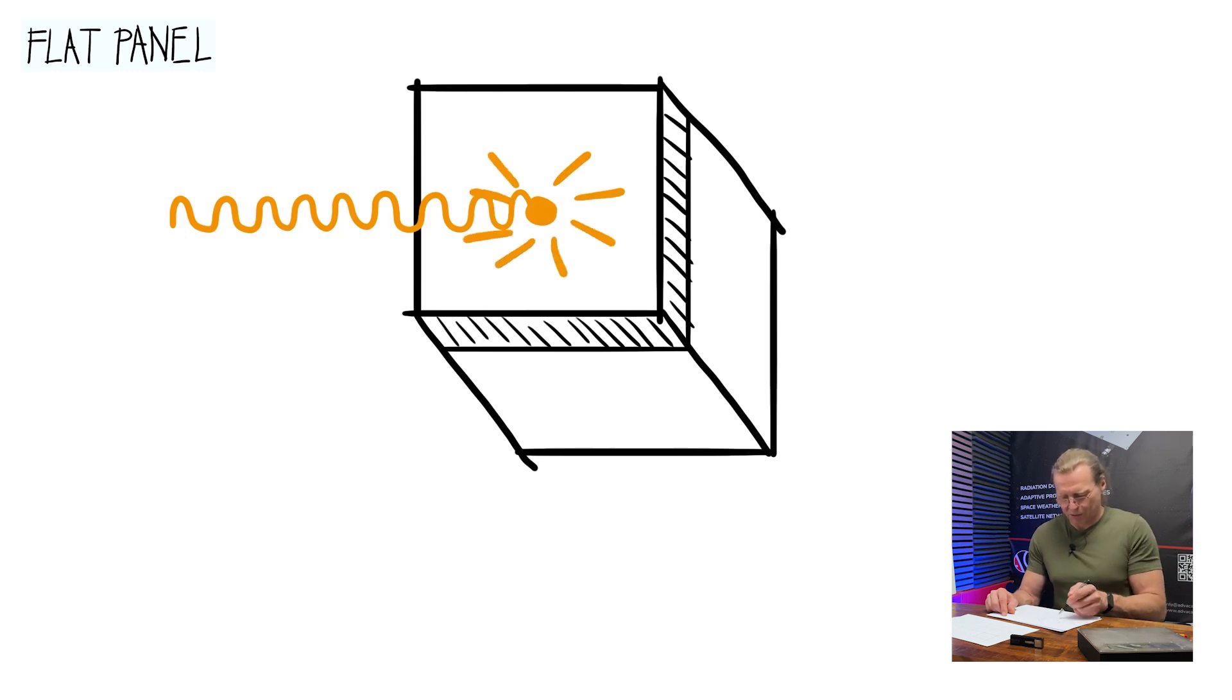And this visible light goes to another layer beneath. And the other layer consists of a standard photodiode. So photodiode, which converts this visible light to electrical signal. And the electrical signal has to be accumulated by the pixel. So when such detector is illuminated by x-rays for certain exposure time, the current produced by this diode would be accumulated in the capacitor.